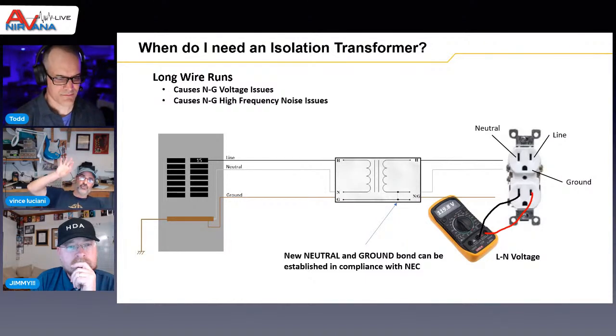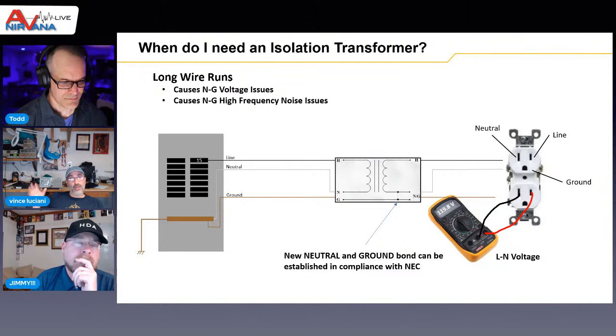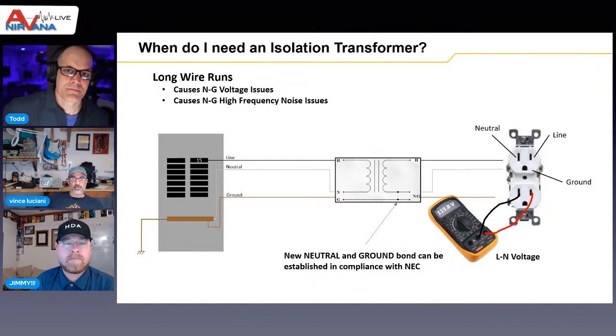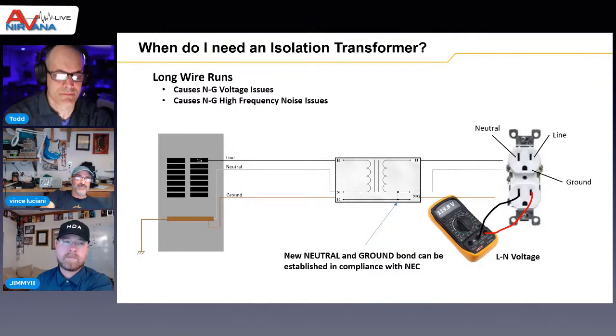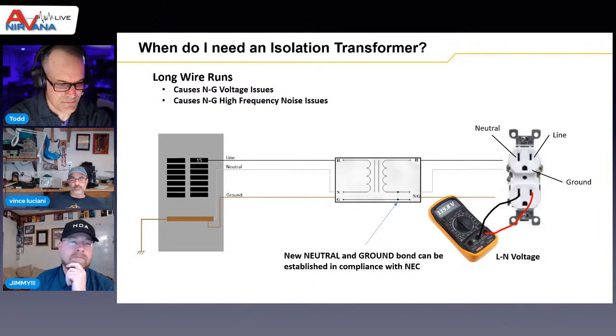So let's say you have your theater on the far end of the house. Most theaters these days have a dedicated equipment room with all the racks of equipment in it. We'll park that large format UPS in that equipment room, where it's sound isolated, and put the critical load panel right there in that room. Now I have a neutral-to-ground bond, shorting together those neutral and ground wires, and all the noise goes away.